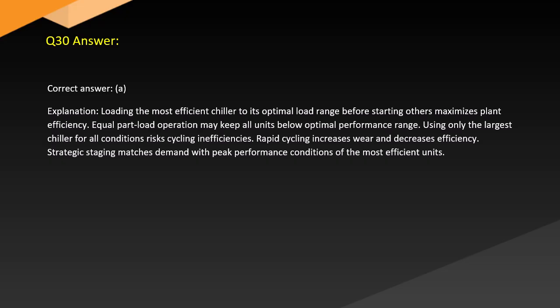Answer. Correct answer. A. Explanation. Loading the most efficient chiller to its optimal load range before starting others maximizes plant efficiency. Equal part load operation may keep all units below optimal performance range. Using only the largest chiller for all conditions risks cycling inefficiencies. Rapid cycling increases wear and decreases efficiency. Strategic staging matches demand with peak performance conditions of the most efficient units.